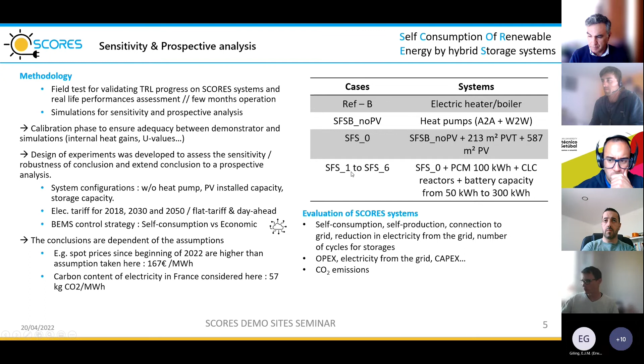In terms of learnings from this sensitivity analysis, here's the design of experiments. We have three main cases, and then we've integrated some battery capacity variation from 50 kWh to 300 kWh. In terms of performance, in the reference B case we have a large need for electricity from the grid, more than 600 megawatt hours per year. Introducing the heat pump reduces this electricity from the grid drastically, and PV also brings additional performance in reducing the supply from the grid.